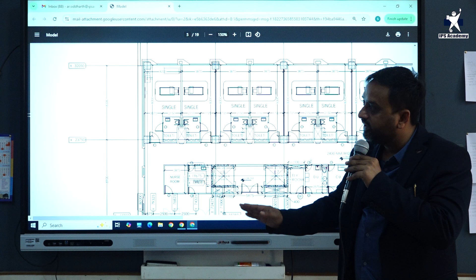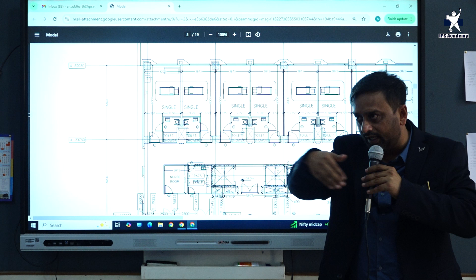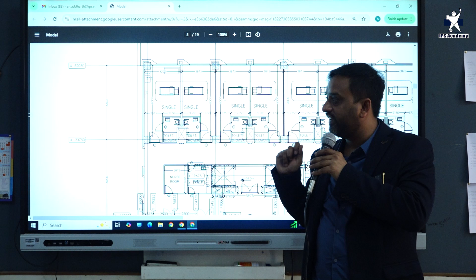Everybody would know how an STP works generally. But in a hospital, when there's sterile waste or chemical waste, you need an ETP also. The effluent has to be treated first or held first, otherwise it will kill the bacteria's membrane and the STP won't work. So sewage from the service floor is diverted and reaches one manhole chamber. Similarly basement one reaches another manhole, and then it goes to the equalization of the sewage treatment plant. Multiple processes are there for STP - MBR, MBBR, SBR - having 6 to 7 partitions. Then a softening unit is also there, and after that UF, ultrafiltration, is introduced these days, after which you use the water.